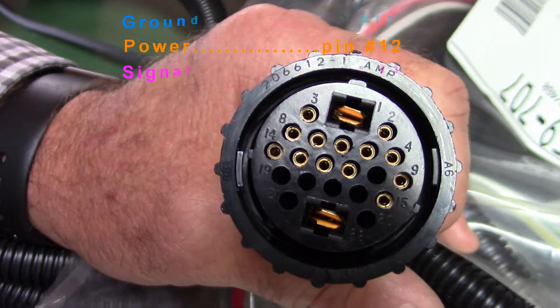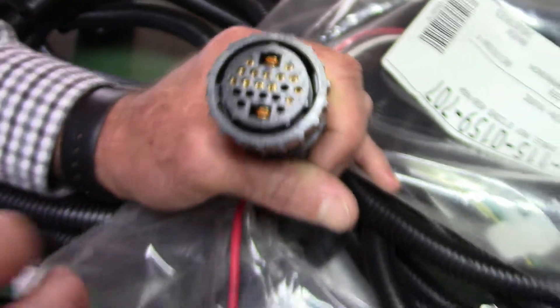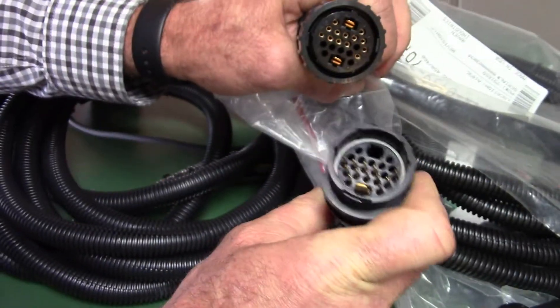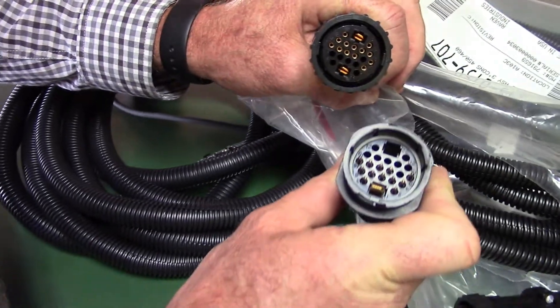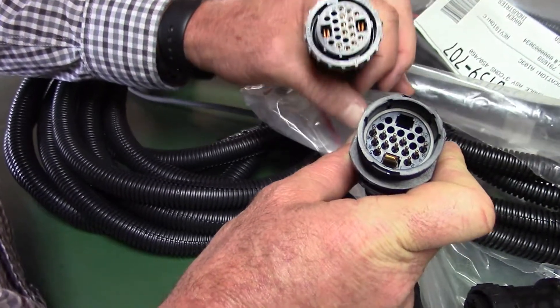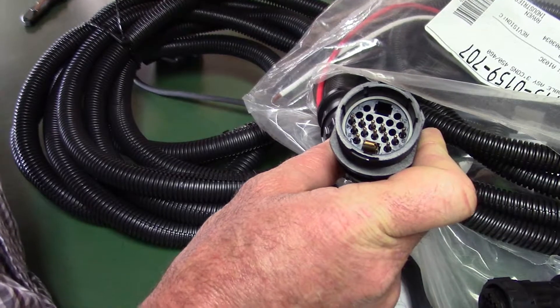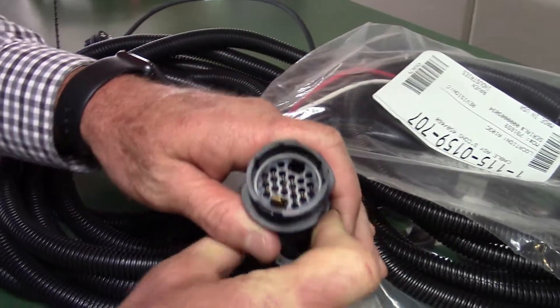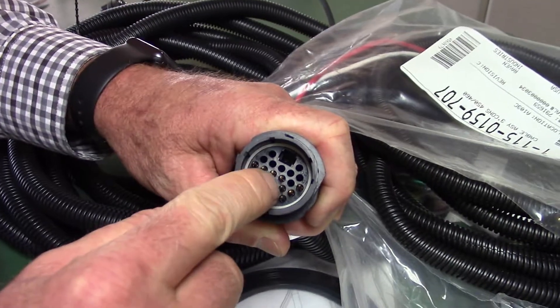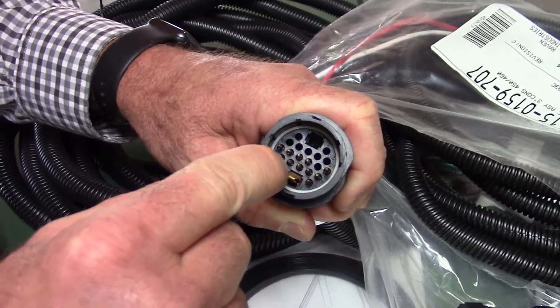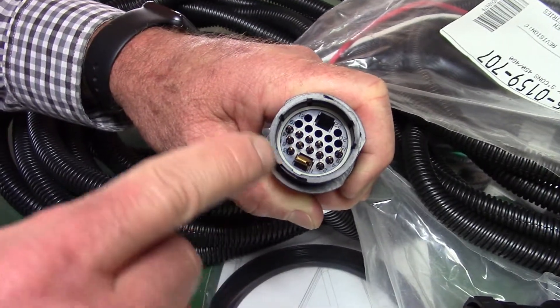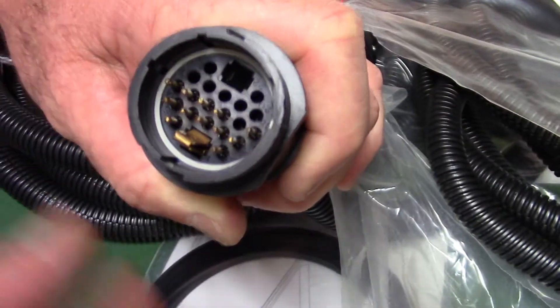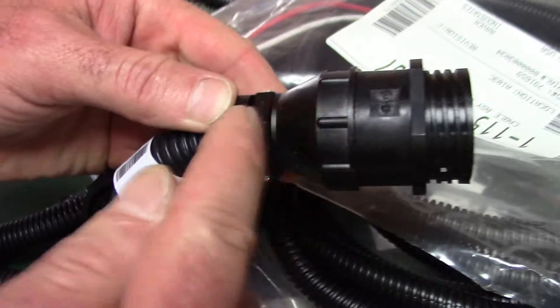If that's correct then you might look at where these two connections go together. Just like the connection that we had with the encoder, those three prongs, if something was wrong there would be a problem here with these pins. From time to time we find where one of these pins might be pushed back down in this part of this cable.